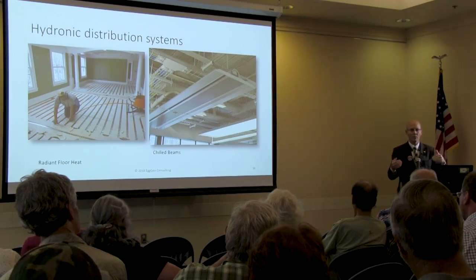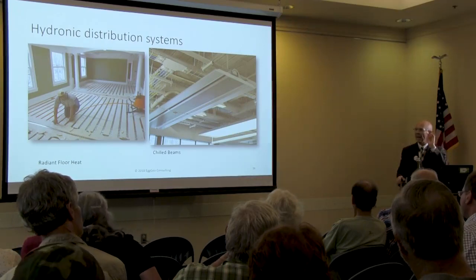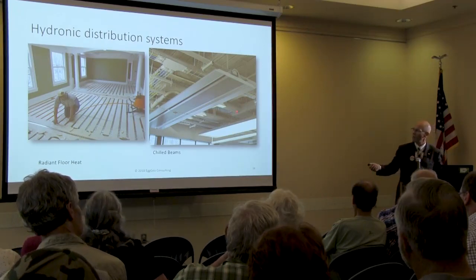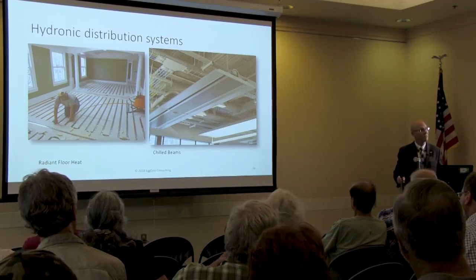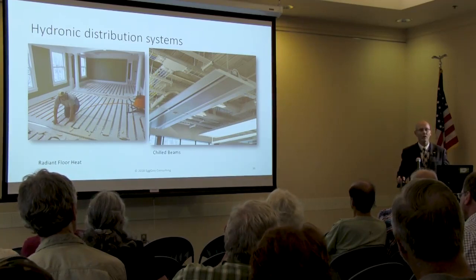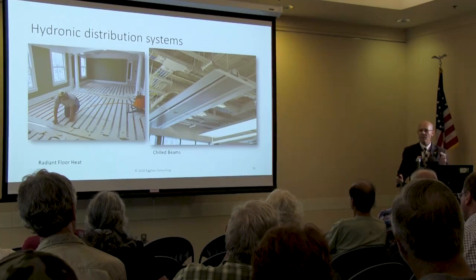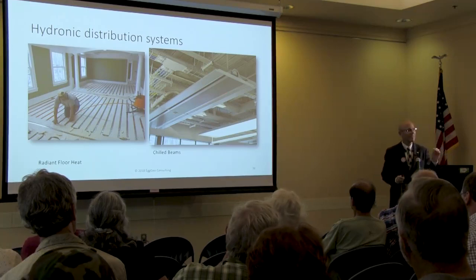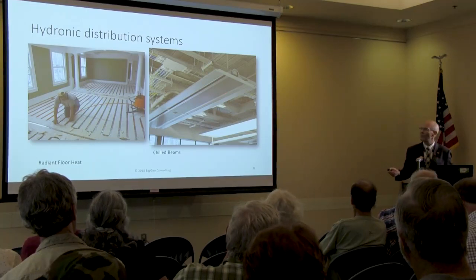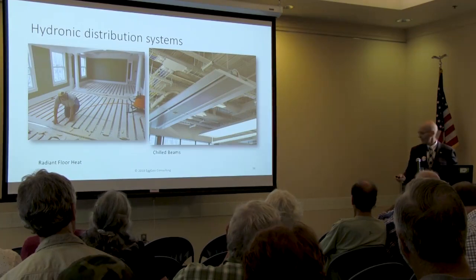There is a trick to it, lest anybody fool you. These things have to be controlled with what they call injection mixing blocks, so that the panels stay above the dew point. They know the dew point, they have to stay above it, and you have to have a 100% fresh air system in a building, because it's got to control the humidity and bring you fresh air. So these things all work in unison. As a matter of fact, it's almost an exact science, but when I toured this building to...